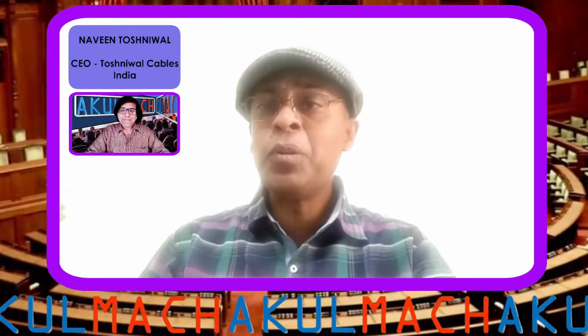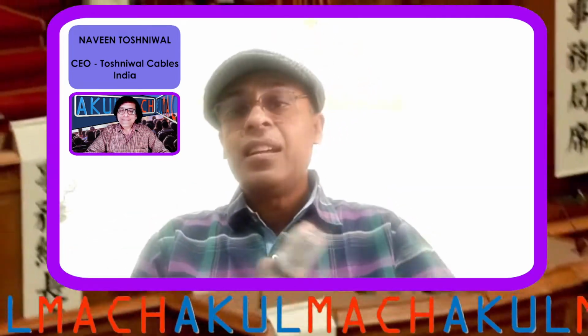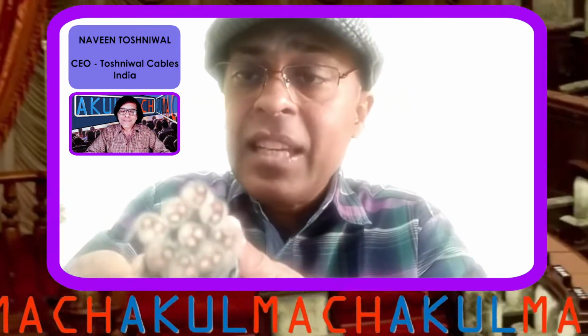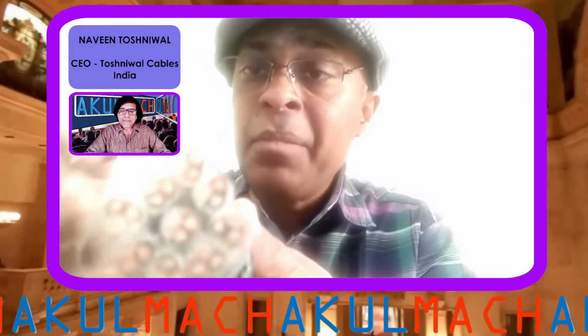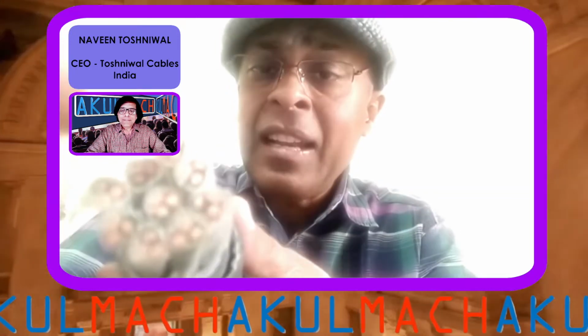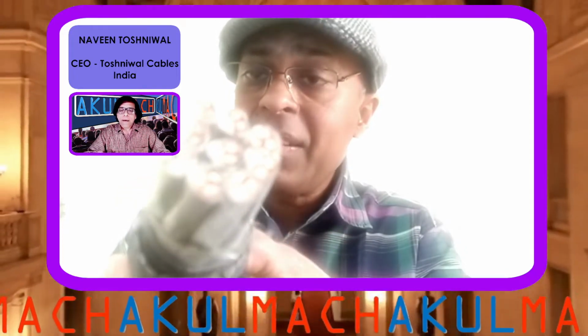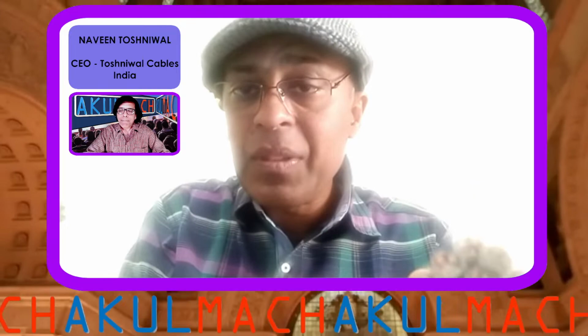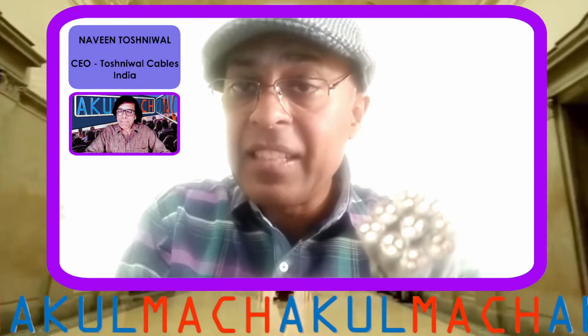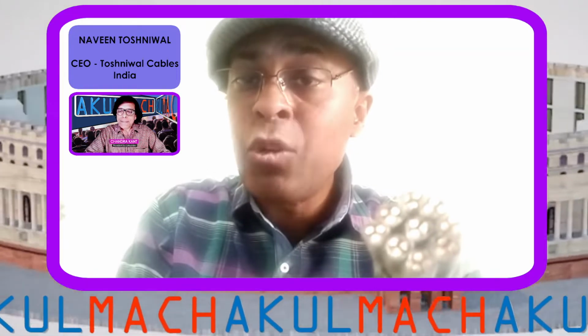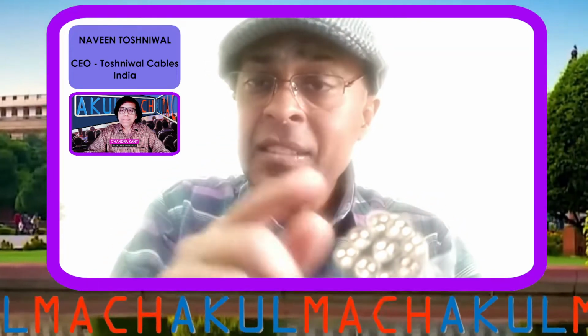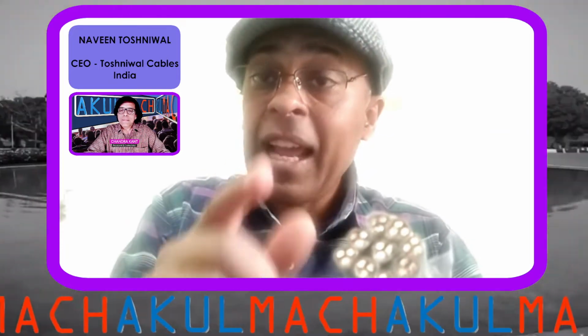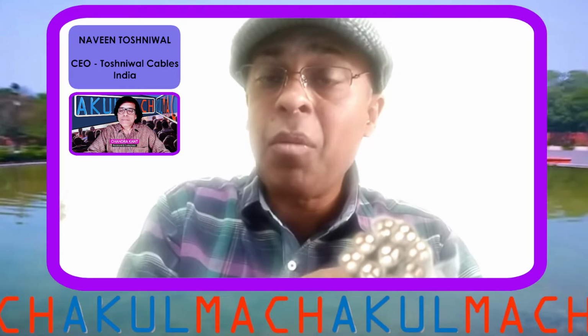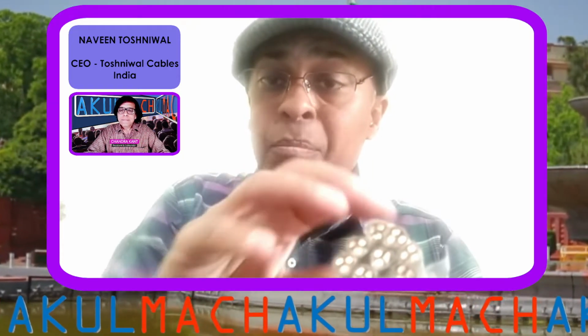Yeah, I'll show you another sample which will give you some idea. Now, we were talking about RTD cables. I am showing a close up. This is again a multi-triad cable. Triad means three, a bunch of three. So you will see there are 9 triads in this. 9 triads means a total of 27 cores in bunches of three. So in fact, this cable can be used to connect 9 RTDs at a time, and the cables carrying the 9 individual RTDs are put in this common cable.